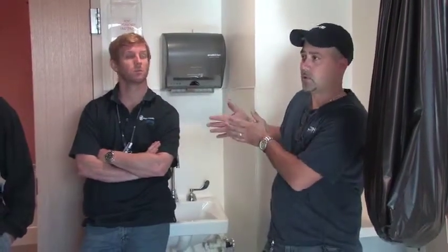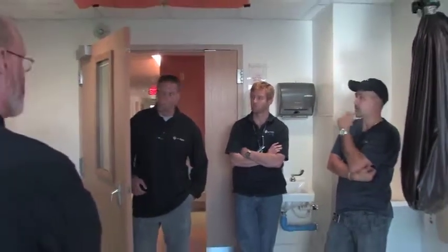Steve Fostello would change that out. He wanted to implement the standard that they were using over on the other side of the hospital, which is simultaneous. It's gonna be open all the time, but only if outside air temp is below the lockout. When the temperature's above the lockout, it's gonna lock all of it out and they're all gonna close. But regardless, if it's below whatever you set it at, 50 degrees, 60 degrees outside air temp, they're gonna be open regardless of the temperature in the room.